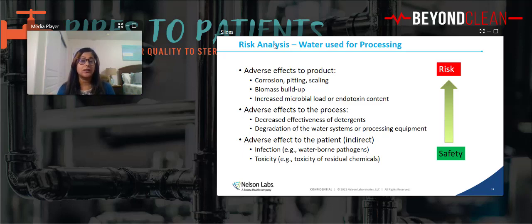Increased microbial load means increased endotoxin. So if you have all of these different things in there and you're not controlling your water, now you've increased endotoxin. And like we talked about, endotoxin has a pyrogenic effect, right? So it's going to cause illnesses to patients with that gram-negative organism. So it is very important that all of these measurements are taken care of for the product. Now for the process, you have decreased effectiveness with detergents, like we talked about, and degradation of water systems and processing equipment, including filters. When do you change filters for AERs, right?